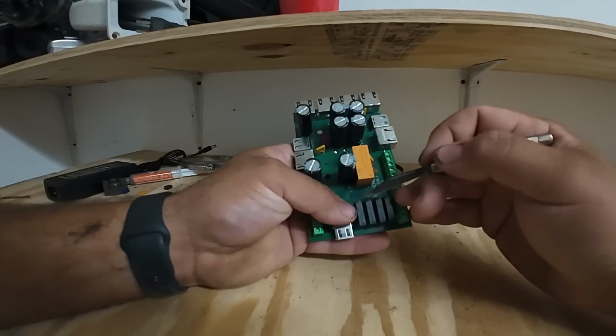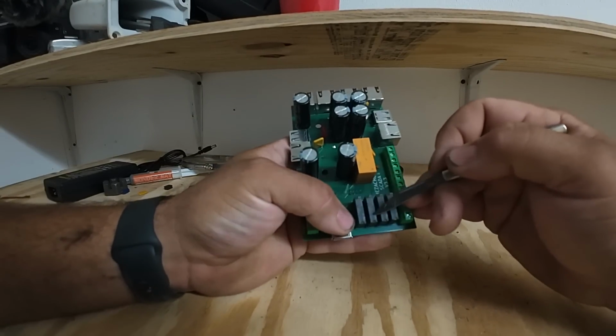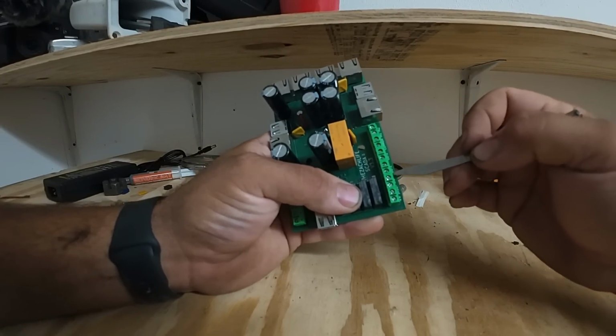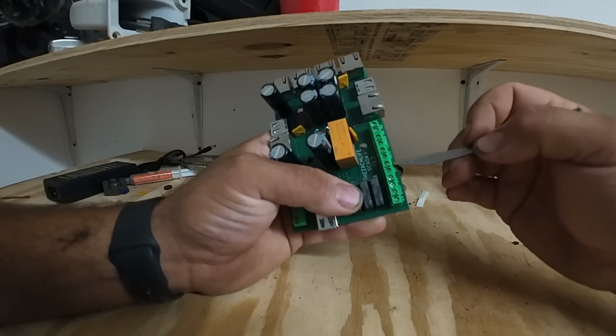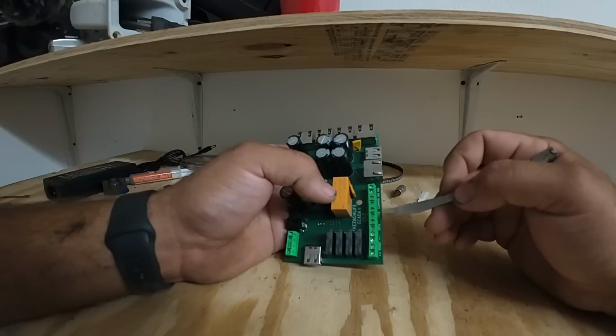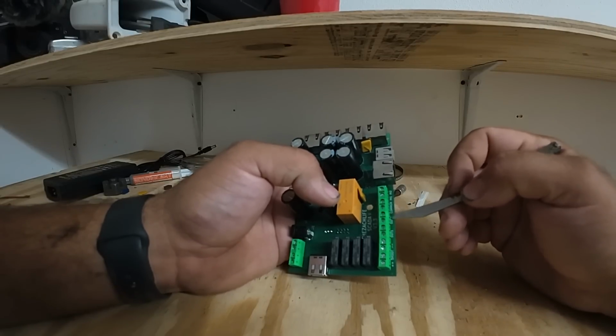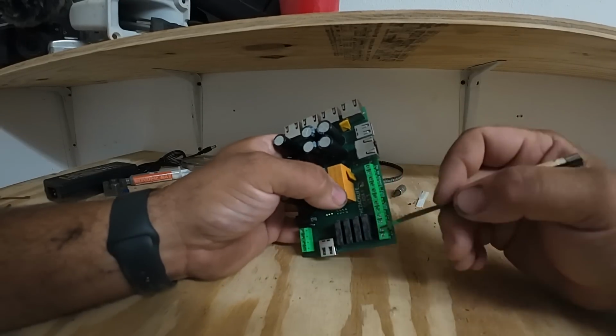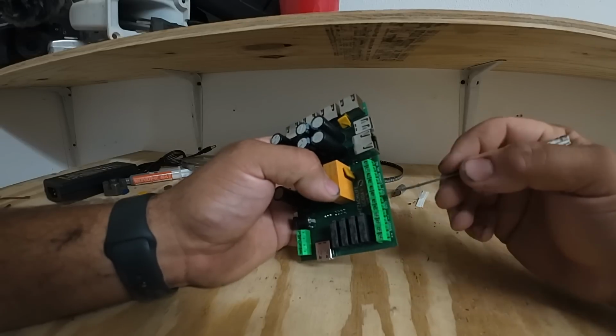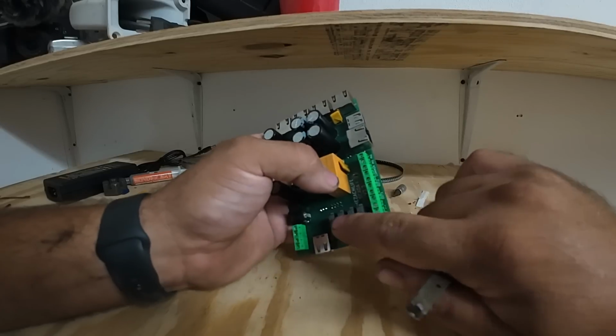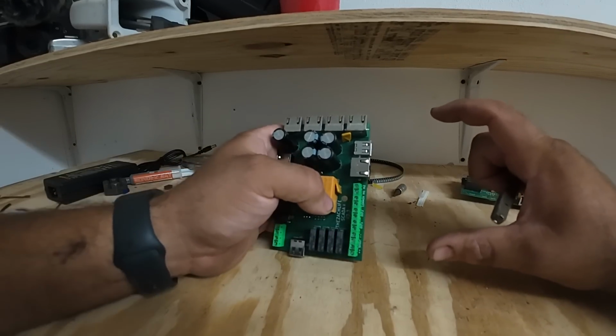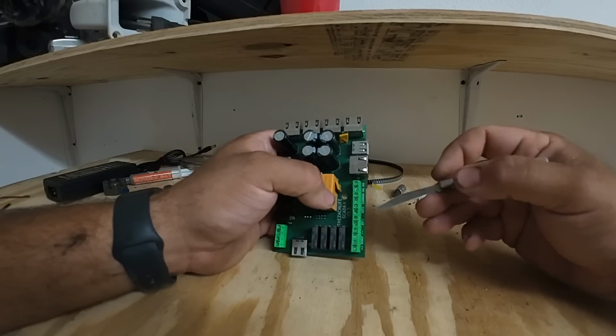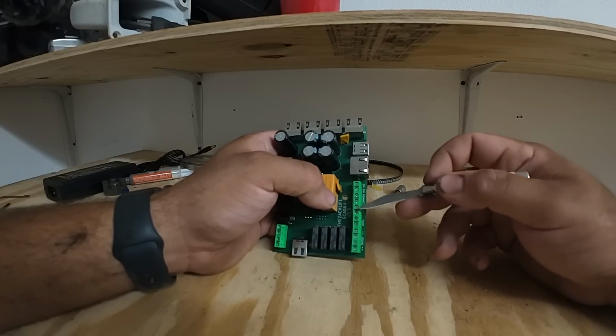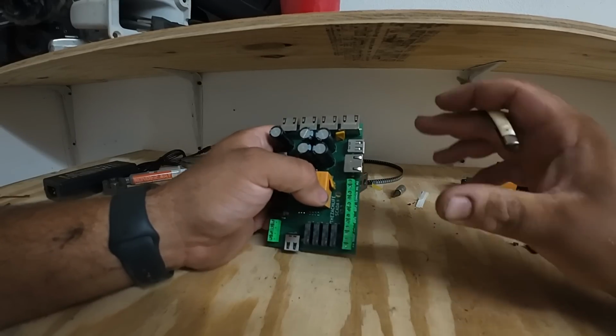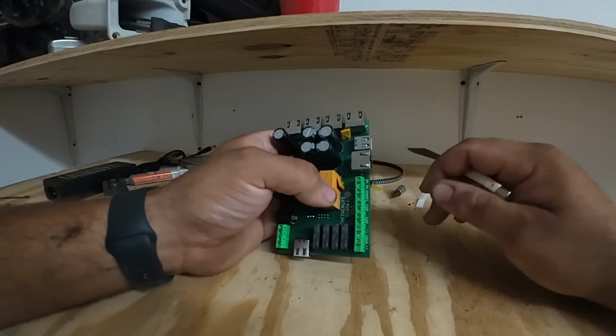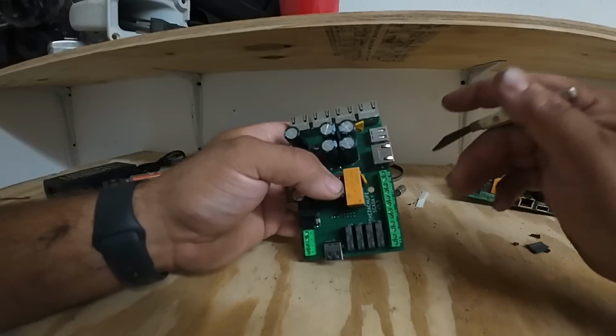This allows the current to go down here and turn off and on these couple of relays. So we've got 2 outputs here controlled by the LabJack through these relays - the contacts of one relay and the contacts of the other relay. This allows us to control something relatively high power, we're talking about 5 amps here, by the LabJack. You can step these out into your control panel, and if you need to control something large, run a 12 volt or 24 volt signal through these relays to control a large relay or contactor, if you need to control an unlimited size motor.